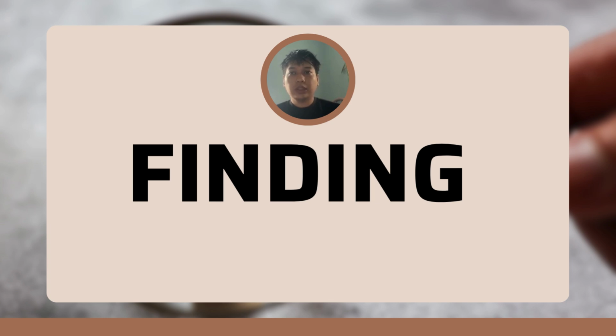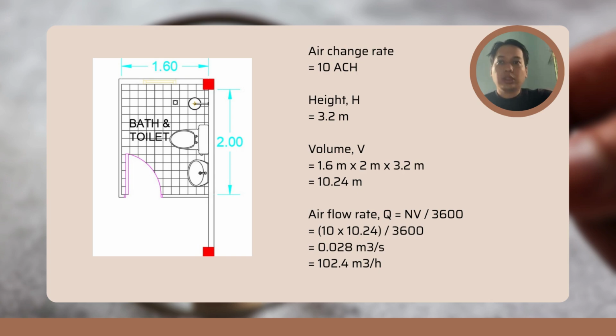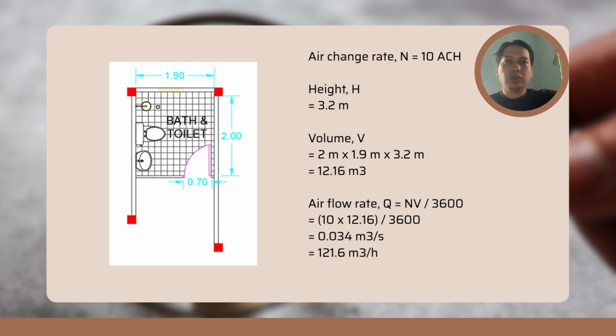The part that I was presenting was the finding and the calculation about our design. So the first bathroom, the air change rate was 10 ACH while the height was 3.2 meter and the volume was 10.24 meter cube. While the airflow rate Q equal to NV divided by 3600 was 102.4 meter cube per hour. For the second bathroom, the air change rate was 10 ACH and the height was the same as bathroom 1, which is 3.2 meter. The volume was 12.16 meter cube and the airflow rate is 121.6 meter cube per hour.